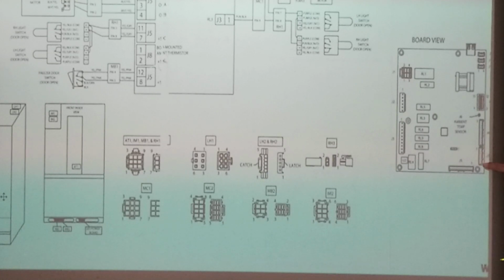I go to J6 and I check pins 11 and 12. I can unplug that, put my own meter on it, on the wires. What would I be testing? I'm gonna unplug it from the board, go to pin 11 and 12 on that board. What am I testing? Let's see if the electricity is coming out, test and see if you got a broken wire.